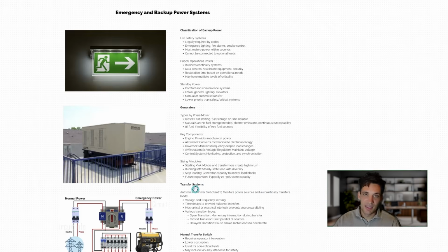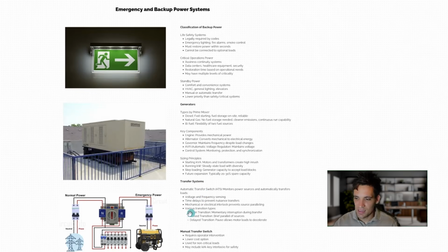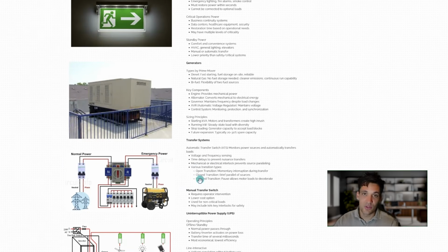So when we're talking about generators, we talk about the rating of the generator in kVA, the running kilowatts, what it produces in steady state, the step loading, so what current it draws to start, and any future expansion if you want spare capacity. So how do we connect a generator to a power system? Well, that's where we have transfer systems.